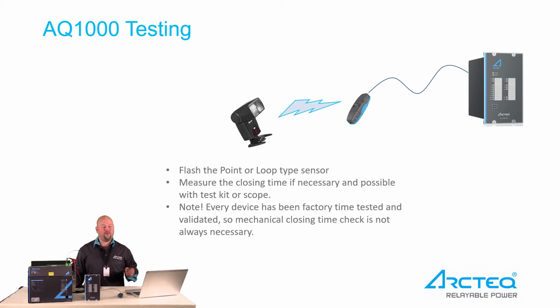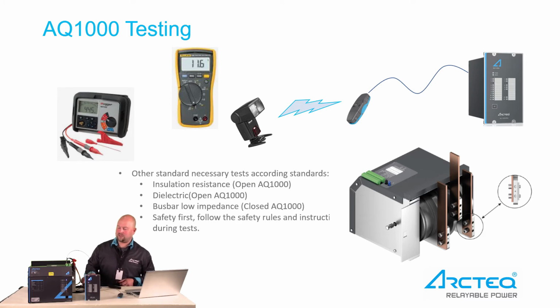No notification, every AQ1000 device has been factory time tested before entering site. Other testings which may be necessary, for example, multimeter, maybe insulation resistance measurements, maybe dielectric testing. All these, insulation resistance and dielectric, are done when AQ1000 is opened. And bus bar low impedance after the unit is closed. During testing, you can test, for example, low impedance from the bus bar wherever it is a good location for the test, just to test that the resistance is practically zero.